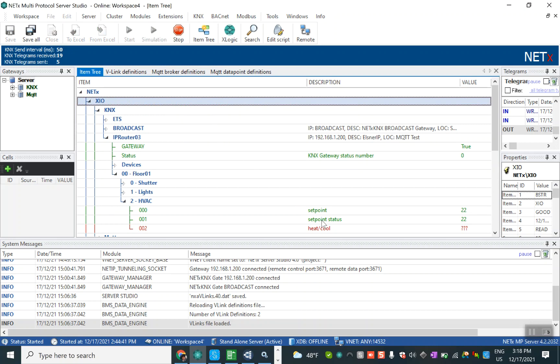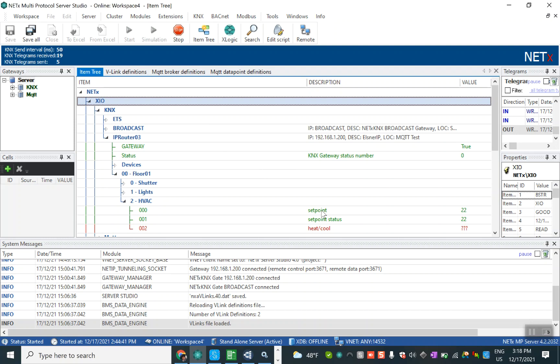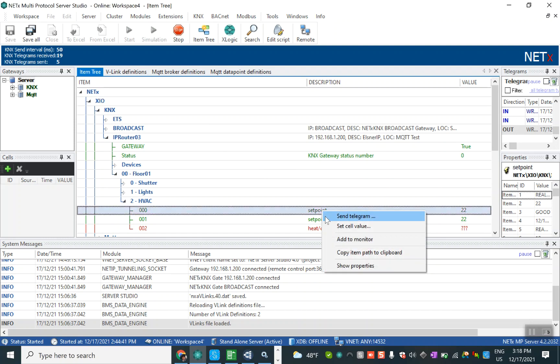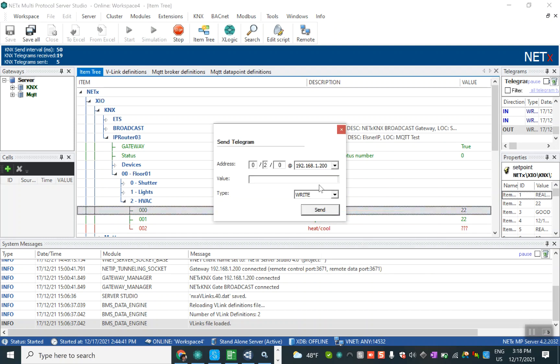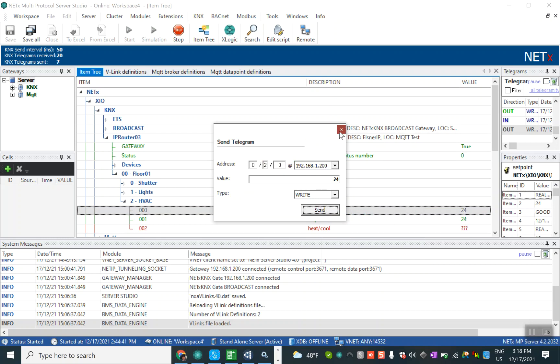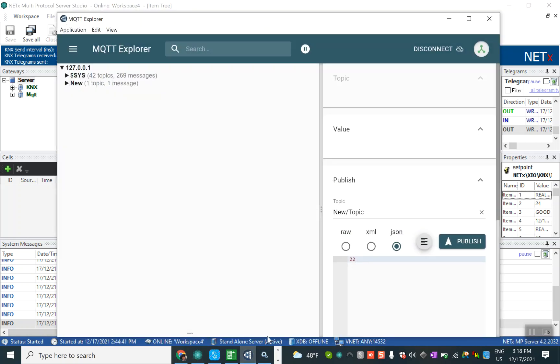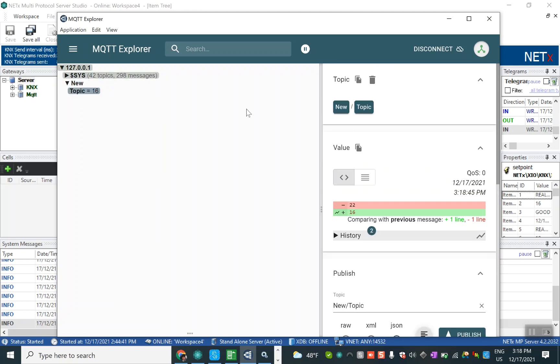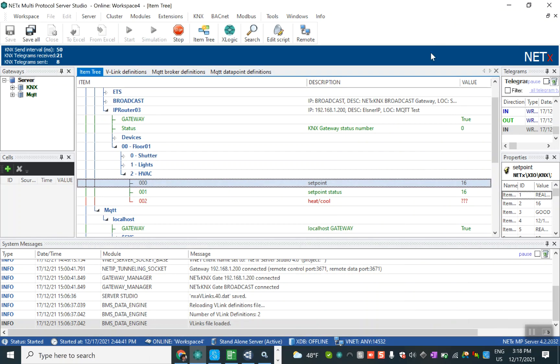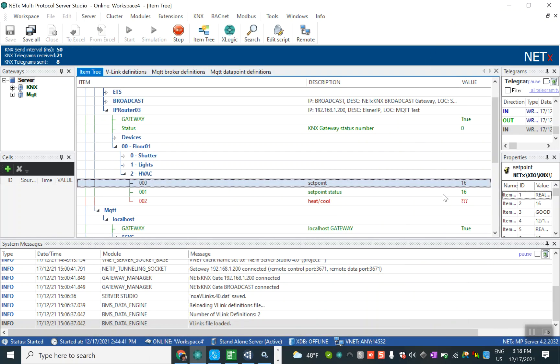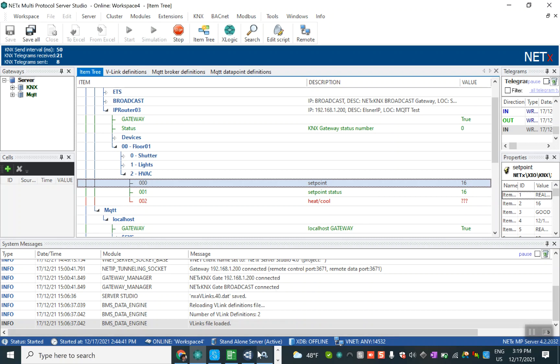I for example send the new set point 24. You can see the set point is updated here. We can go to the MQTT explorer, we can define set point 16, publish it. You can see here it's published 16. The set point in KNX is changed and you can see the set point status from the thermostat that we have, the Elsner new thermostat ETR.